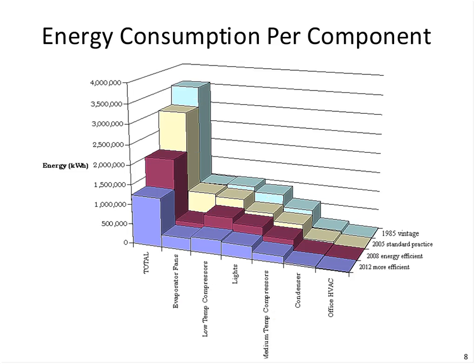But then if we go to 2008, what we'll refer to as energy efficient, here you can see the big step in evaporator fan energy reduction, and that's by the utilization of variable speed drives on evaporator fans. So when the load is not necessarily at its peak in the refrigerated warehouse process, we can see what results: pretty substantial energy savings there, and continued improvement in the compressors.